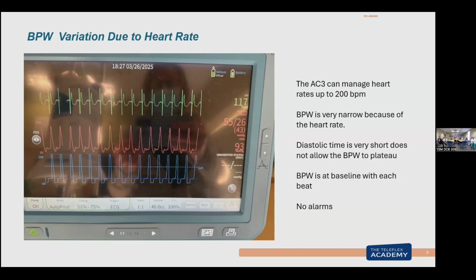This is one of your patients, and the pump is pumping and handling that. Our pump can handle heart rates of 200 on that. As long as I can get back to baseline and get ready and get in and out, we can monitor, we can pump for every one of those beats and support the patient. But it's going to have to get back to baseline because I've got my helium ready for the next beat. That's where it monitors that.